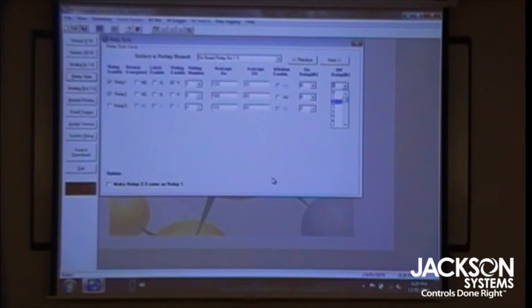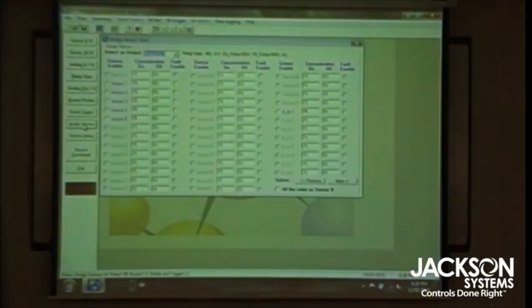So you may have it set at 50 ppm, and at 10, once it reaches 10, it says okay, shut off the relay, shut off the fan in 2 more minutes, and you shut it off. So it's that easy. Then here you assign sensors. These are all the sensors that I turned on. This is relay number 1, which I turned on. And now I can assign my sensors to the relays, and then I can assign my set points.